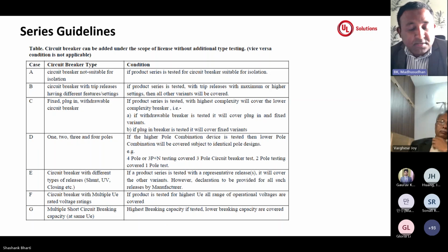Similarly for accessories that they want to add with the breakers, especially shunt, UV and the closing unit for the breakers. And also any breaker with multiple voltage ratings. Suppose a product is certified today with the highest voltage rating and tomorrow manufacturers want to add a lower voltage rating with the same specification without changing the product; that can be accepted without any changes, only to upgrade the voltage. And in a similar way for short circuit breaking capacity. If today a product is certified with a specific short circuit breaking capacity at the upper voltage, and tomorrow the same product is to be upgraded with a lower short circuit value at the same voltage, that can be done without any testing, with the documentation.